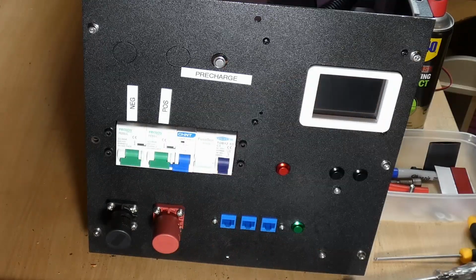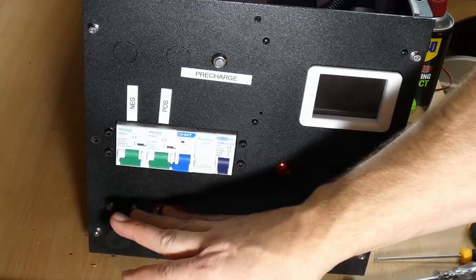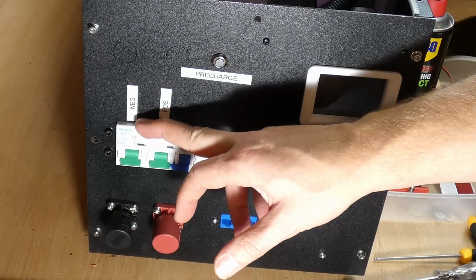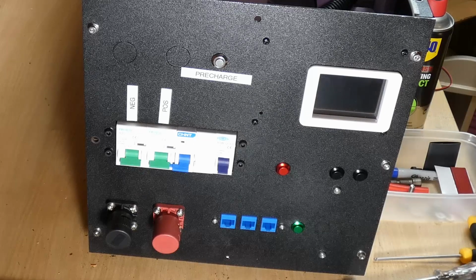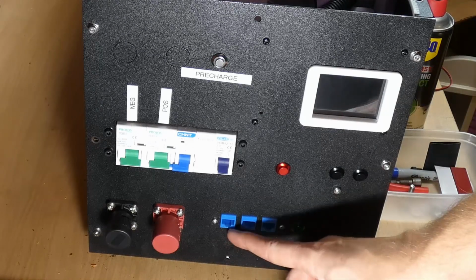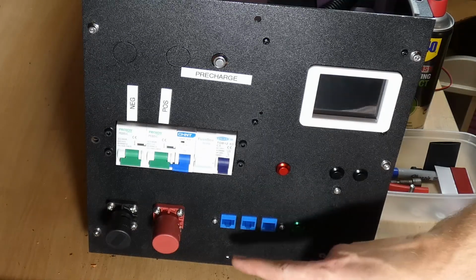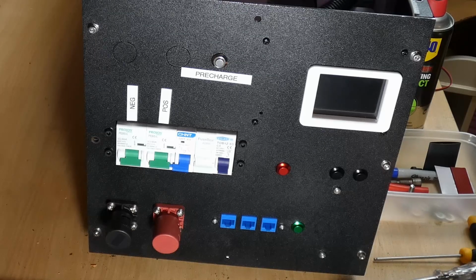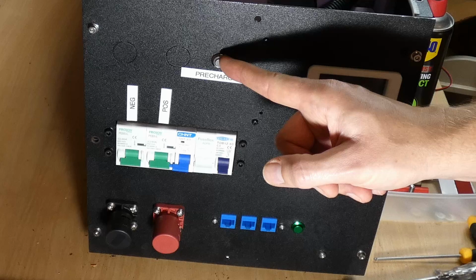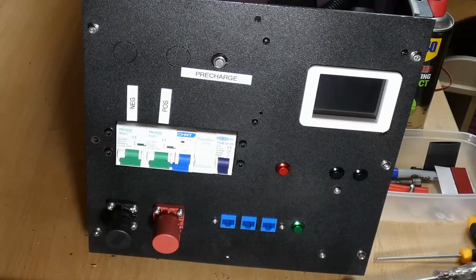These are all DC rated units. You've got the main positive and negative terminals for a connection into the inverter. These are rated for 250 amps, although the inverter I've got only actually needs 60 amps max. These are 80 amp fuses. There's a connection for the CAN bus to the inverter as well. These two are currently unused. I've got a pre-charge circuit that will charge up the capacitors in the inverter to make it easier to switch these on without tripping.